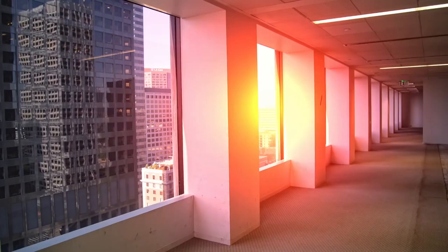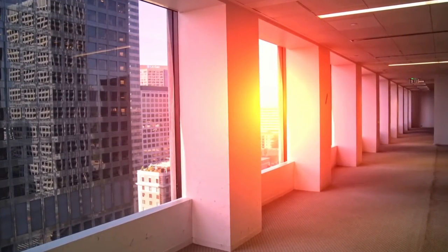When we first started researching window film, we did some tests on two exposures of the facility — the east side and the south side. We recorded temperatures of over 110 degrees on the inside, so the solar load was astronomical.